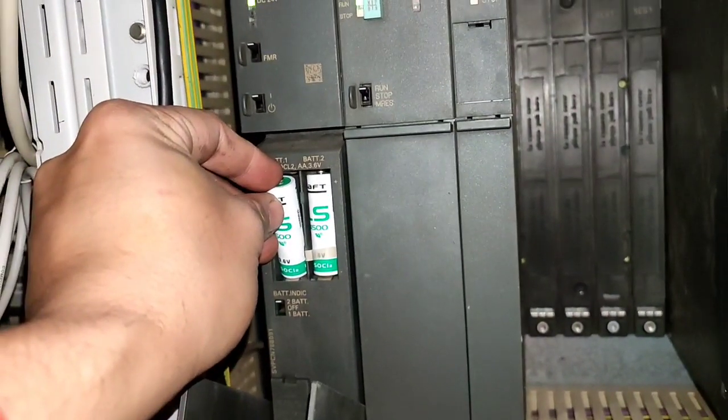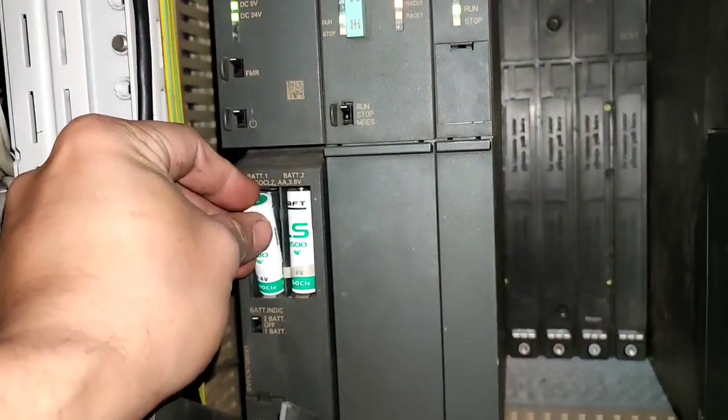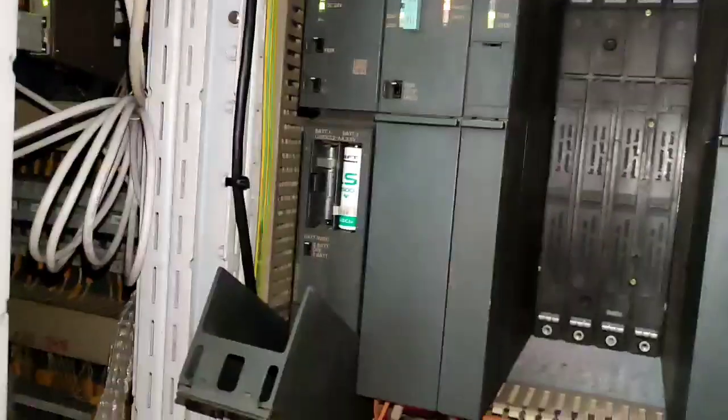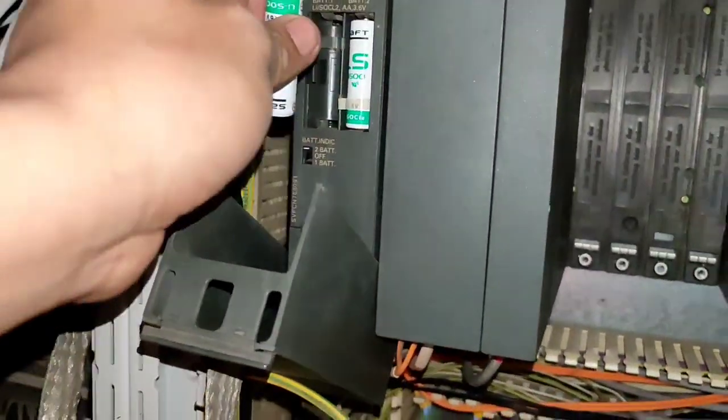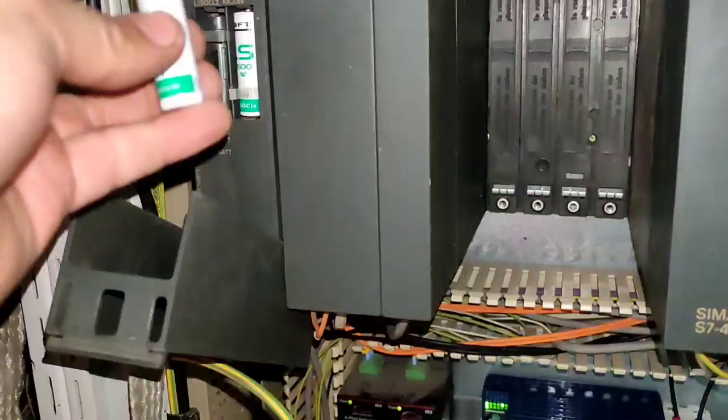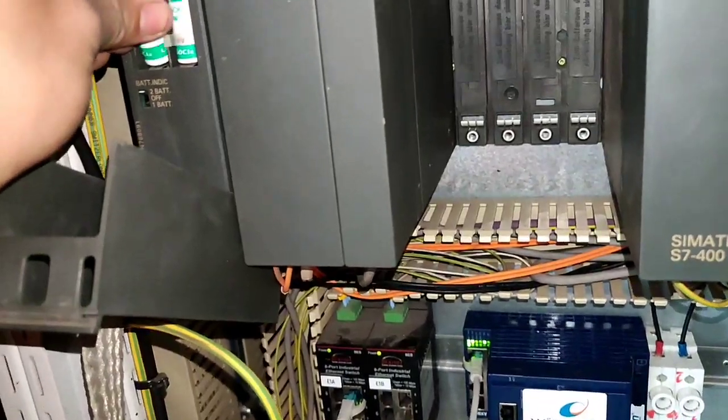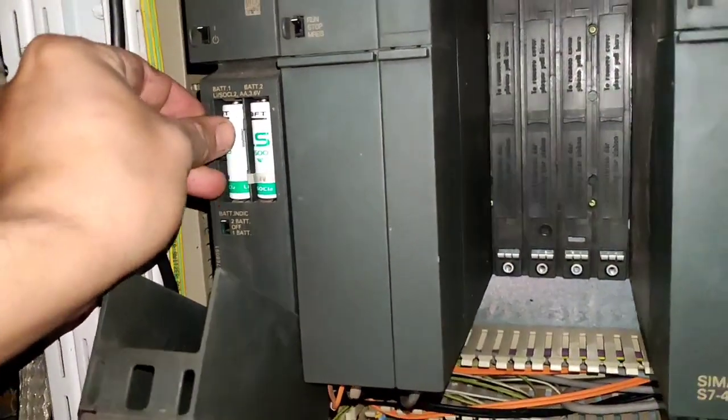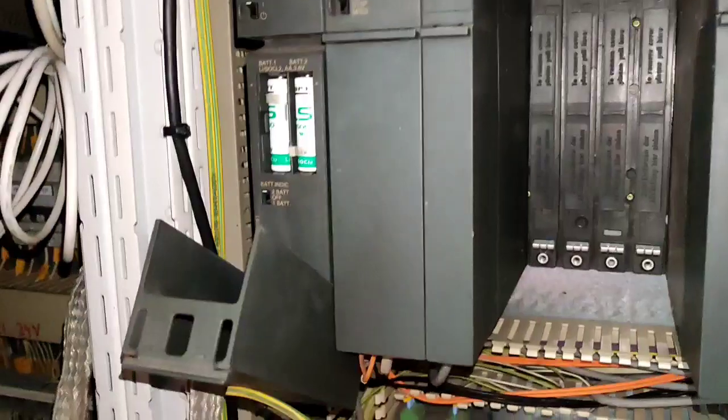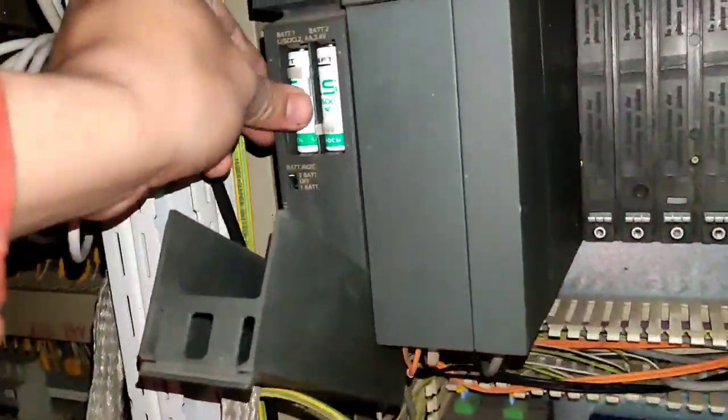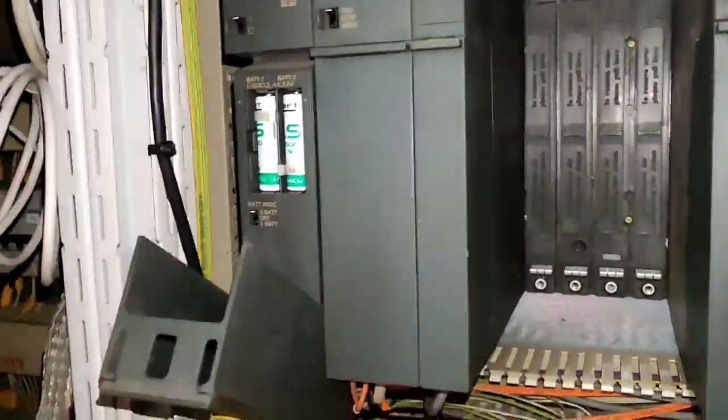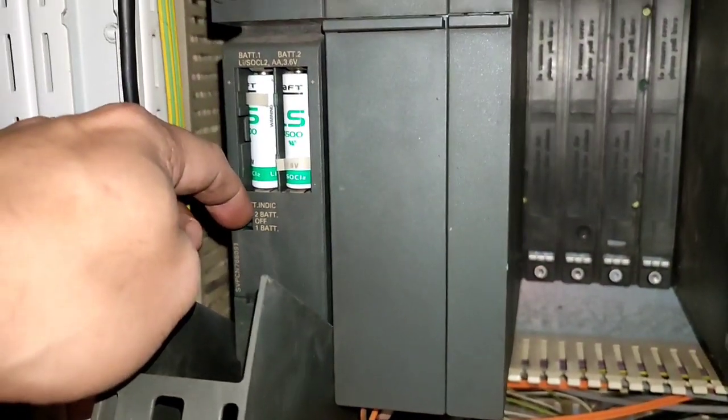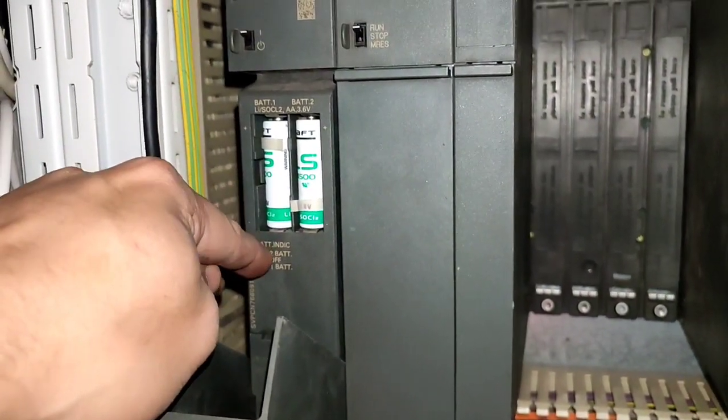If you remove the battery, the indicator BAT1F for number one is illuminated, meaning no battery is detected. If you put it back, the BAT1F alarm is gone.